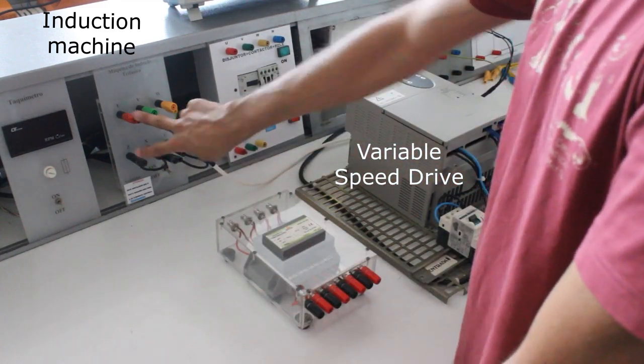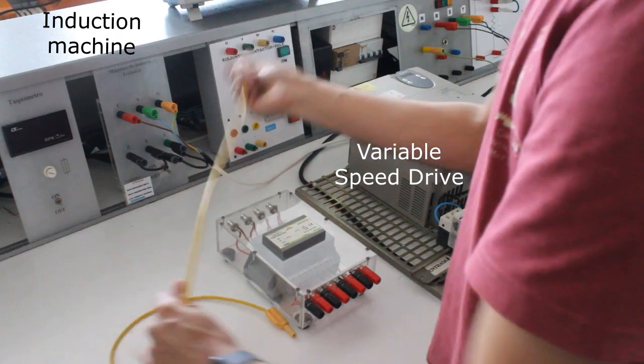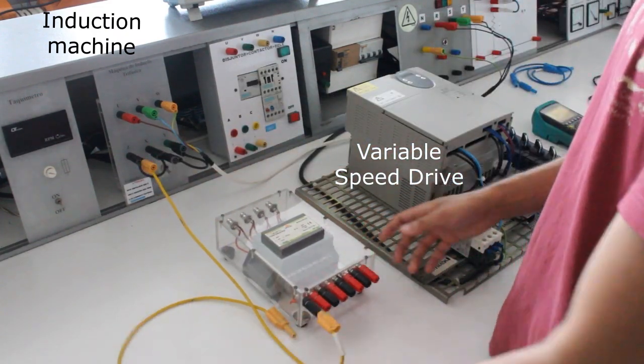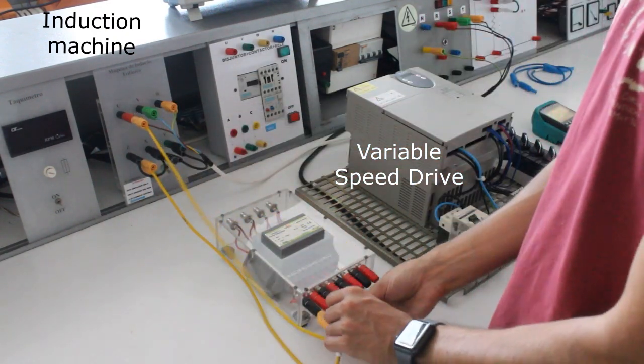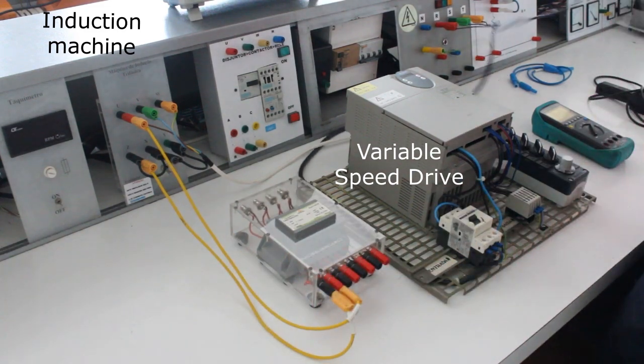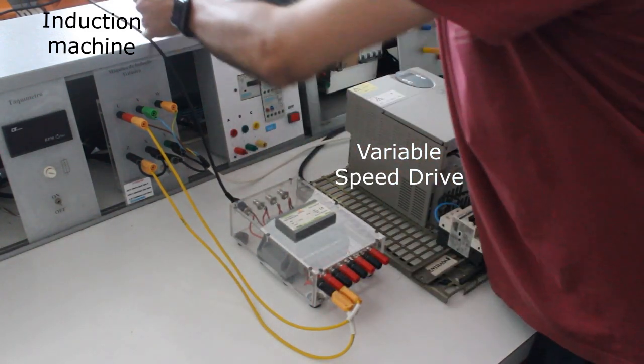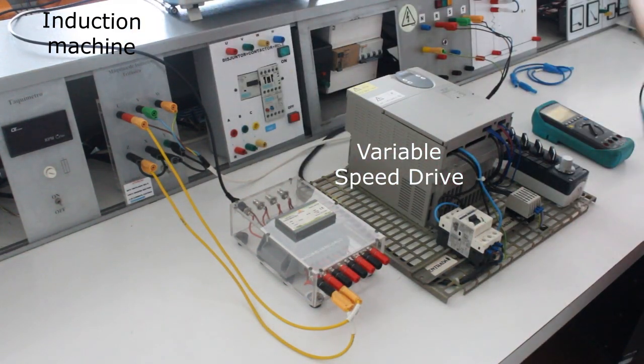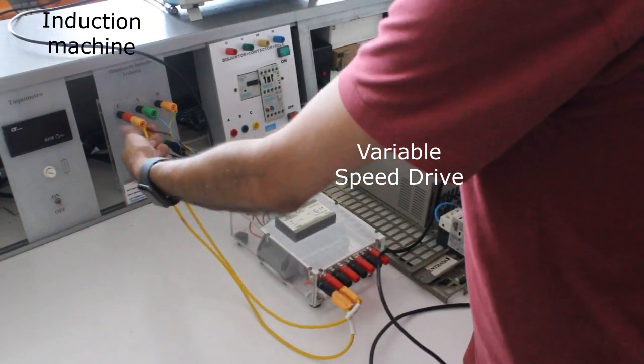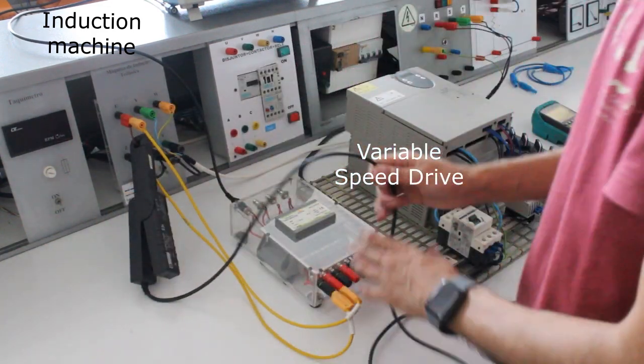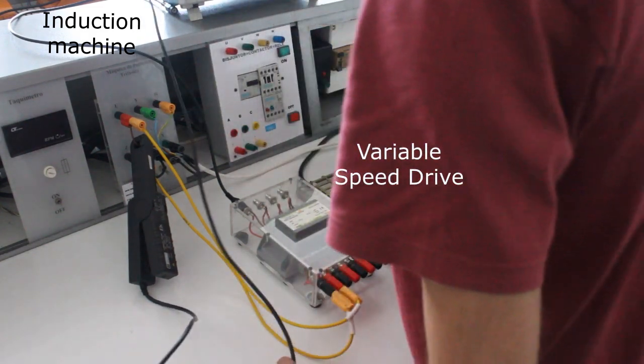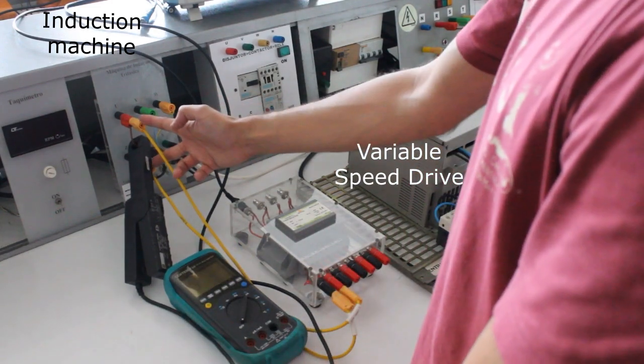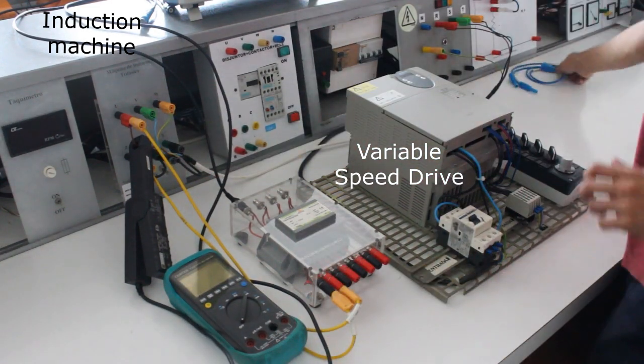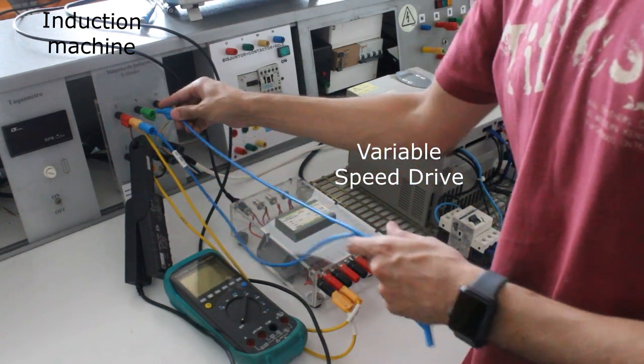Next, use the instrument transformer to measure a single phase voltage of the induction machine in the oscilloscope, and use a current probe to measure the current of this same phase. Remember, it should be in the same phase. Also, don't forget to always use auxiliary measurements to get a fast measure of the voltage and current while you are setting the operation point.